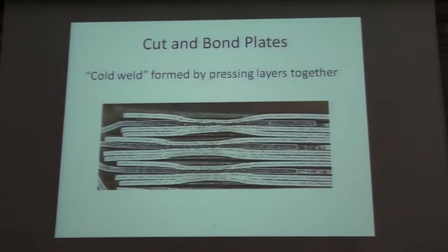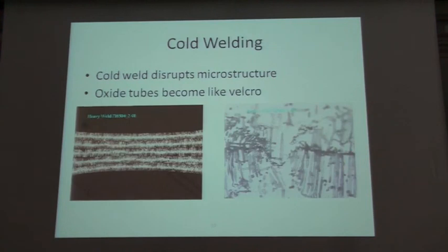The other thing we need to do, since we don't have the continuity of the foil all the way through the capacitor, is connect the plates. We'd like to do this without taking up any space. And it turns out that you can just compress locally. Here I'm showing four plates with a tab that we use to connect to the rest of the capacitor.